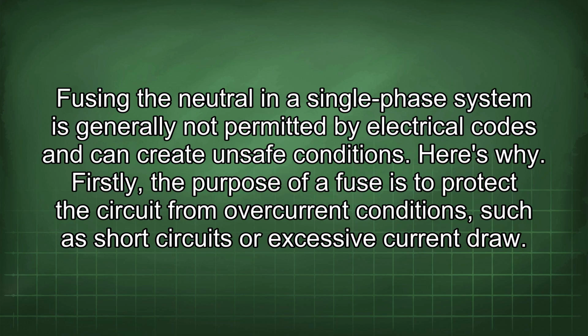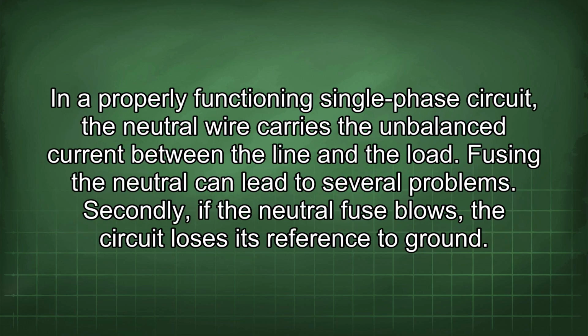Here's why. Firstly, the purpose of a fuse is to protect the circuit from overcurrent conditions such as short circuits or excessive current draw. In a properly functioning single-phase circuit, the neutral wire carries the unbalanced current between the line and the load. Fusing the neutral can lead to several problems.